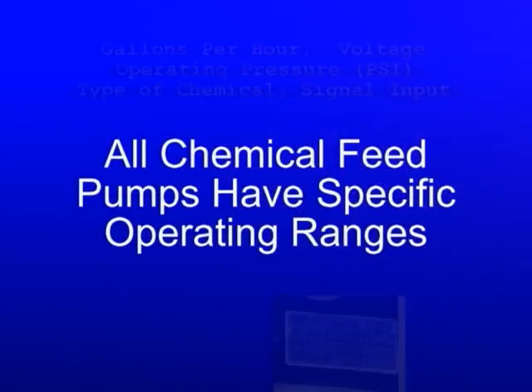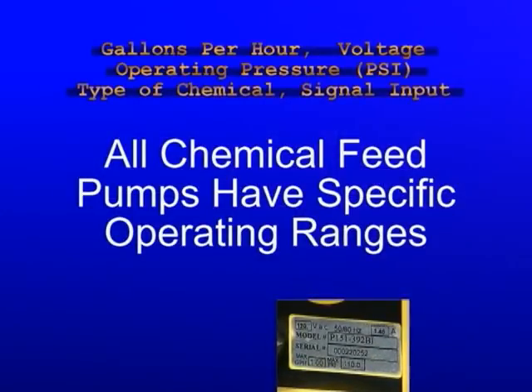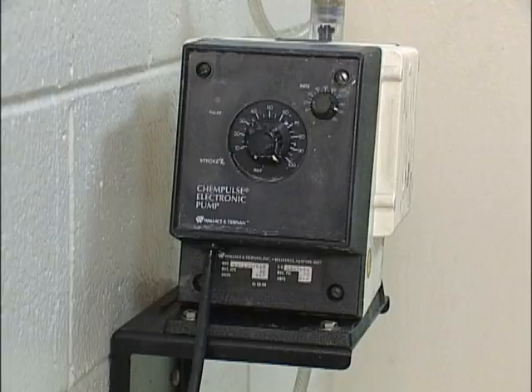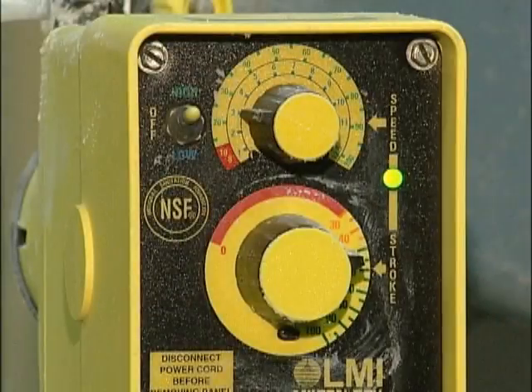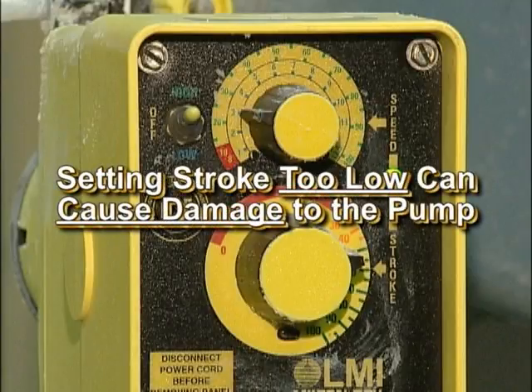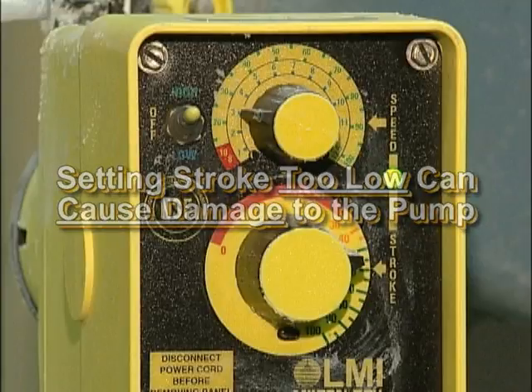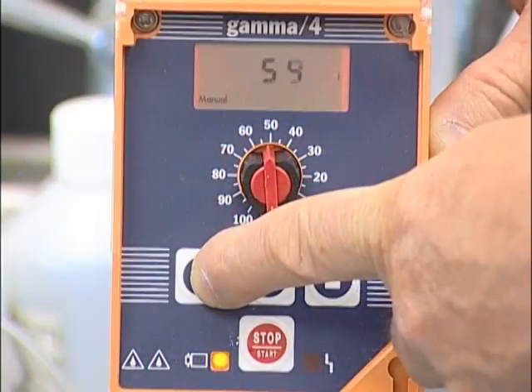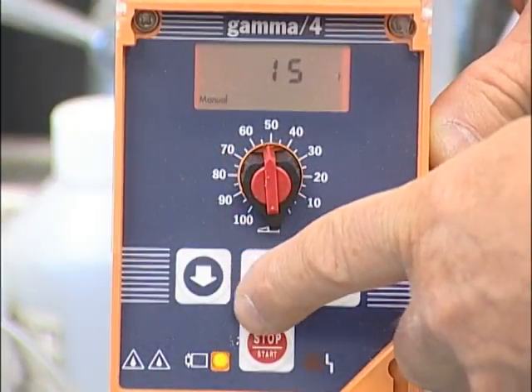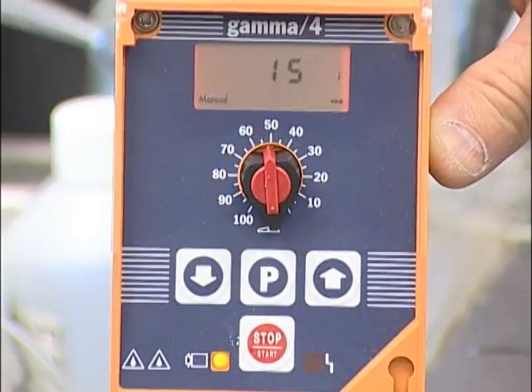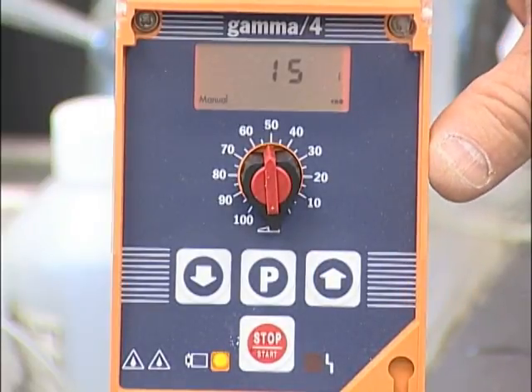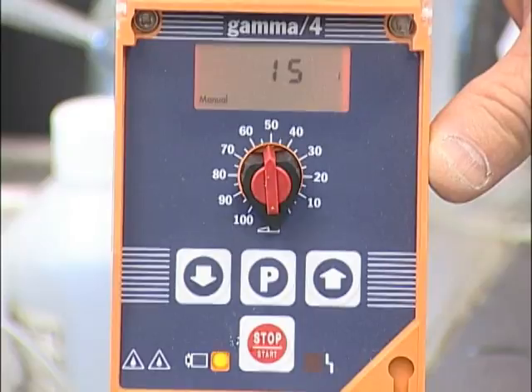Pump manufacturers have recommended operating ranges for their pumps. For those pumps that have speed and stroke adjustments, setting the stroke too low will not provide consistent water treatment and may actually do long-term damage to the pump. If the speed is set too slow, the problem may be the same as with peristaltic pumps. Chemical feed pulses may be so far apart that significant quantities of water may pass through untreated between pulses.